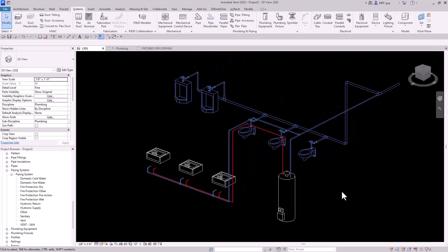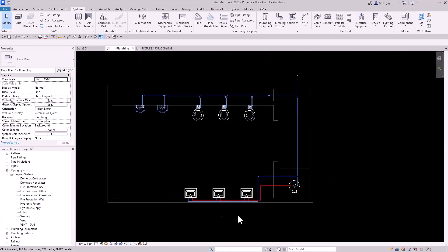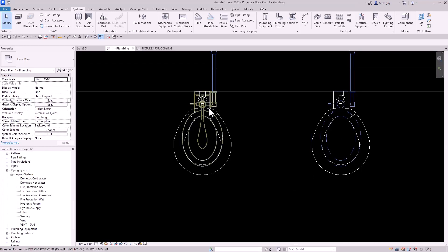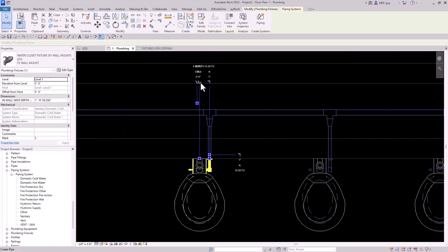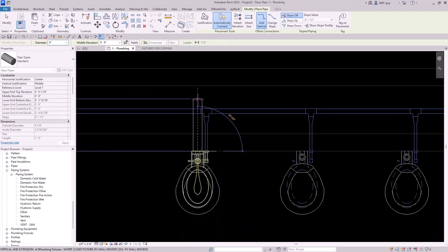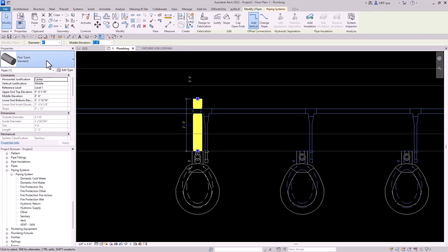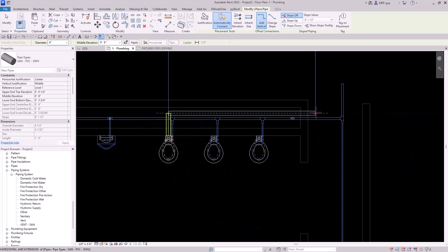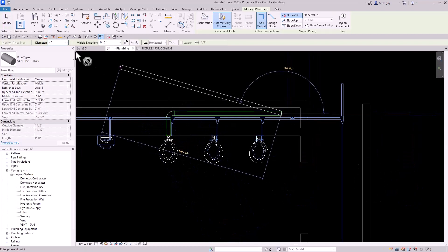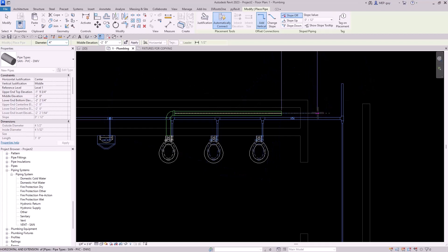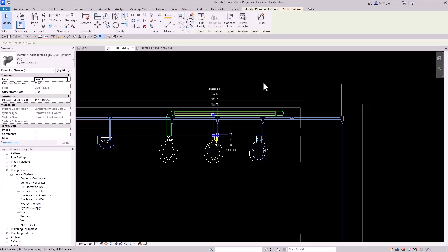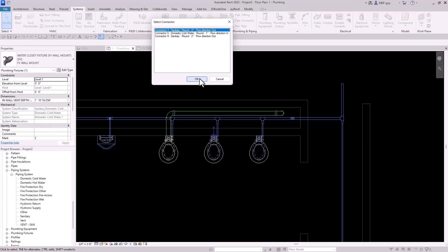Now we have to do the sanitary and vent system. Let's go back to our floor plan and start with our water closets. We'll select the water closet and start drawing sanitary piping by clicking this little connector — we're going to draw it all the way back here. We need to make sure we're drawing the correct pipe type: sanitary PVC. Right click, draw pipe, go off in this direction, drop down in the wall to negative two feet — that's below the floor. We'll go off this way and use our connect into commands with the sanitary.